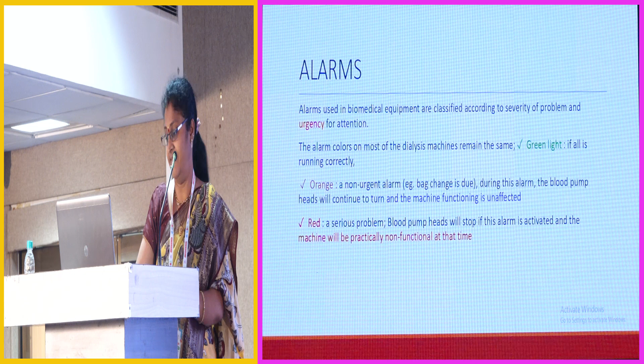So I would like to impress upon you this picture. Morning Shakthirajan sir has told you this. Why do we need so many monitors? Because of what exactly happens in the machine. If you see this circuit, the first is the access, from which we take the blood from the patient, and here we have the facility for anticoagulation. From there, the blood passes through the blood pump. Here we have a pressure called the access pressure, the pressure with which the blood is drawn into the circuit. After the blood pump, the blood is pushed into the filter. Here also we have a pressure, called the filter pressure, and here we have the transmembrane pressure which acts within the dialyzer. From here the blood is pushed back to the patient.